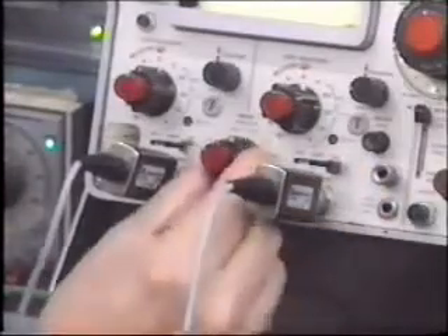Let's connect another probe to the channel 2 vertical input and select the CHOP mode. CHOP causes the 2 vertical traces to time share at a rate of about 250 kilohertz. This mode is preferred for measuring signals up to 100 kilohertz. To continue, connect the local CT signal to channel 1 and the remote CT signal to channel 2. Position the vertical position control for a convenient overlap and adjust the propagation delay pot for exact phase angle coincidence.